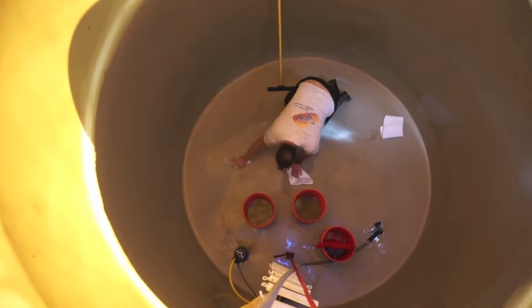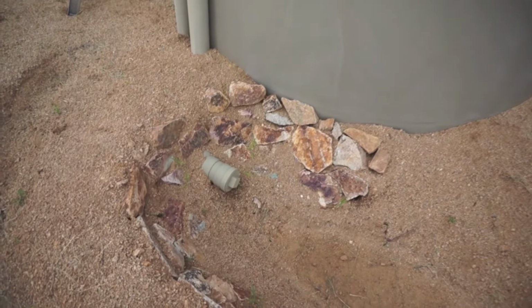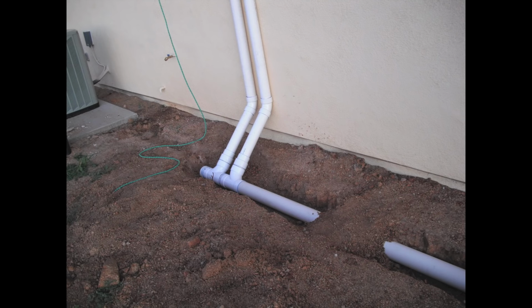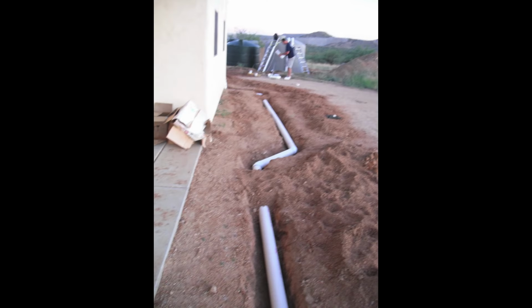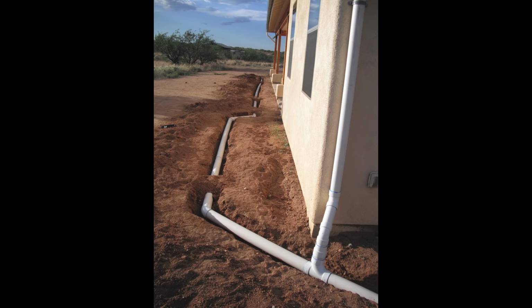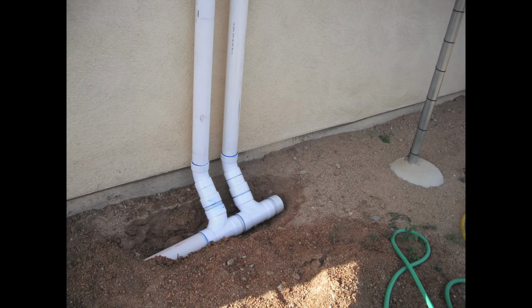The underdrain and overflow drain of the bioretention planter lead back to the cistern and contain an overflow bypass that connects to the public storm drain system for storm events greater than 10 years flow. The cost of this integrated design element was only 3% greater than what would have been required to meet code. However, the benefit to the downstream system is invaluable.